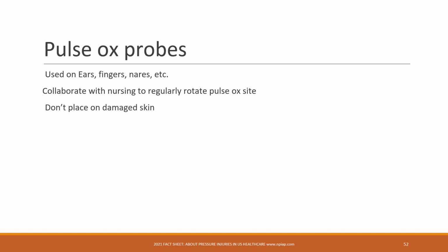And sometimes people will use the pulse ox probes in a way that is not necessarily in accordance with the manufacturer instructions. Like, we will use neonate little sensor probes and we'll put them on the earlobe. But what will happen is they'll get wrapped around the earlobe really tightly, which will just end up cutting off blood flow and will lead to swelling and then skin breakdown. So you have to be mindful of that.